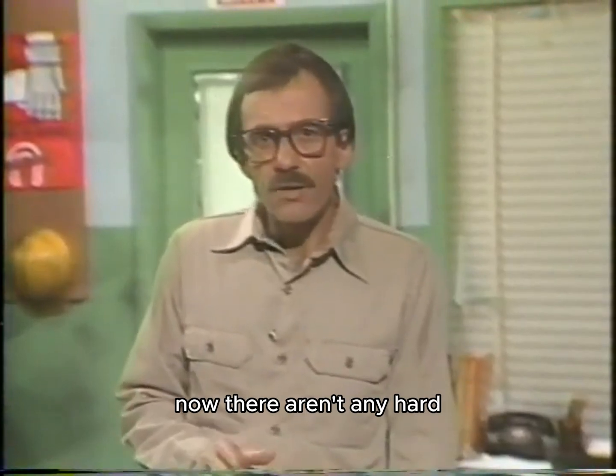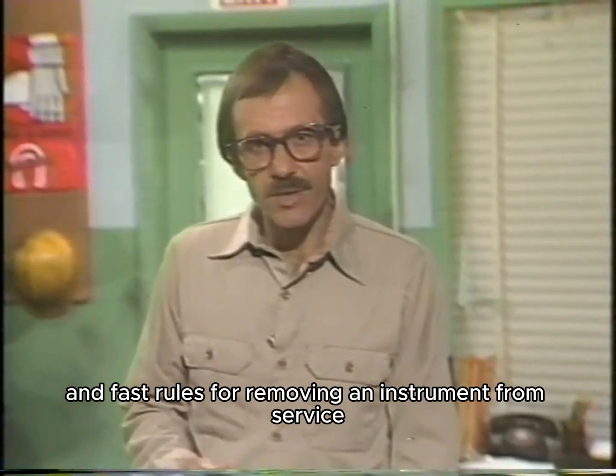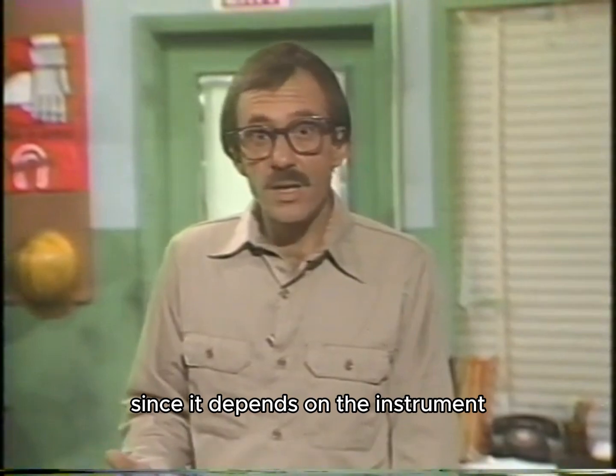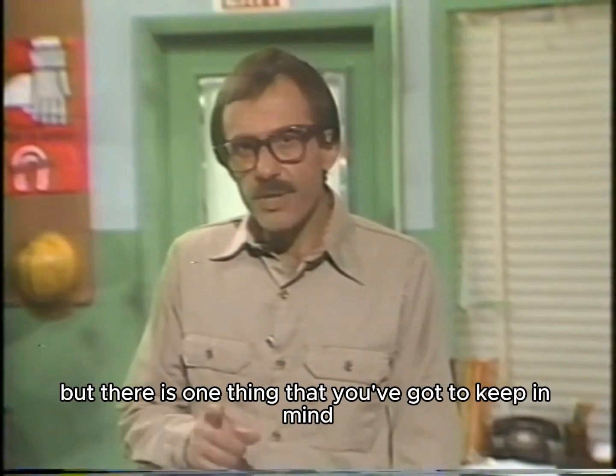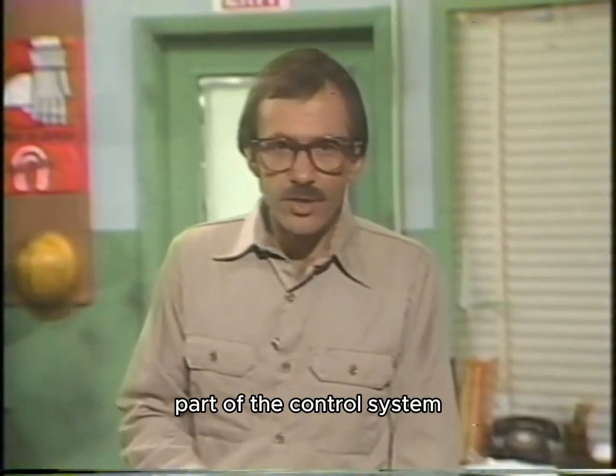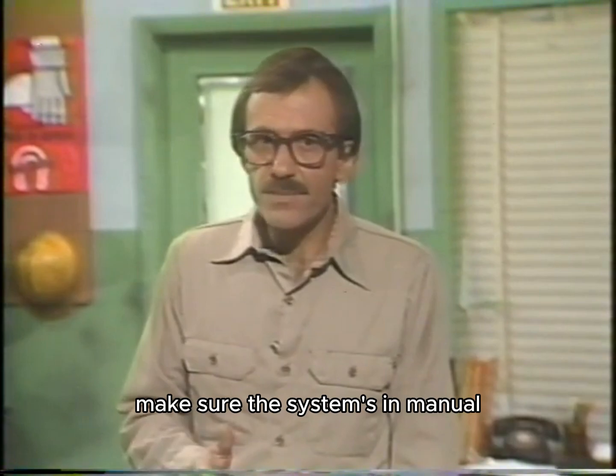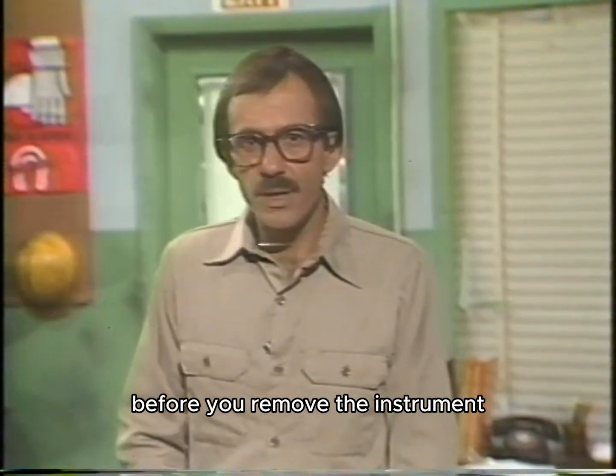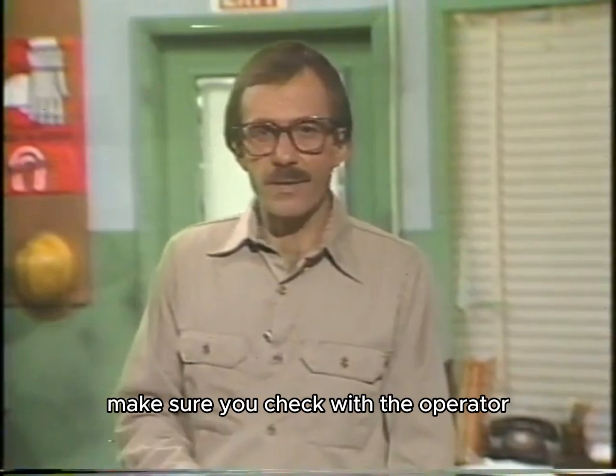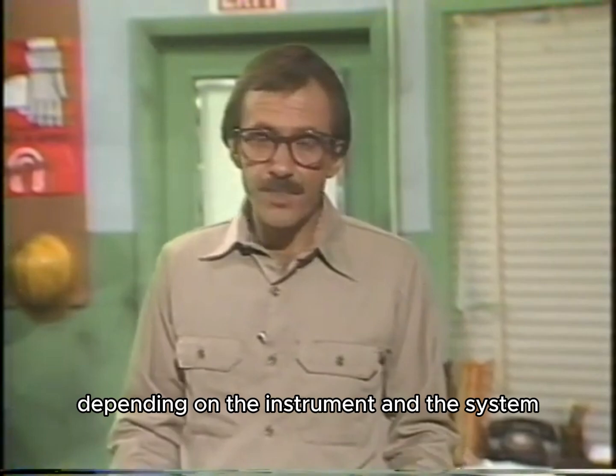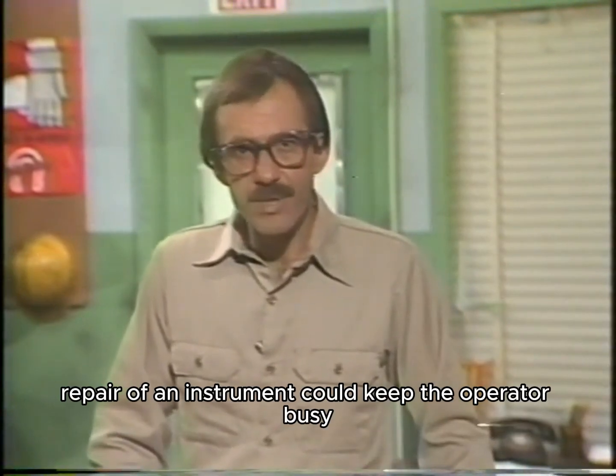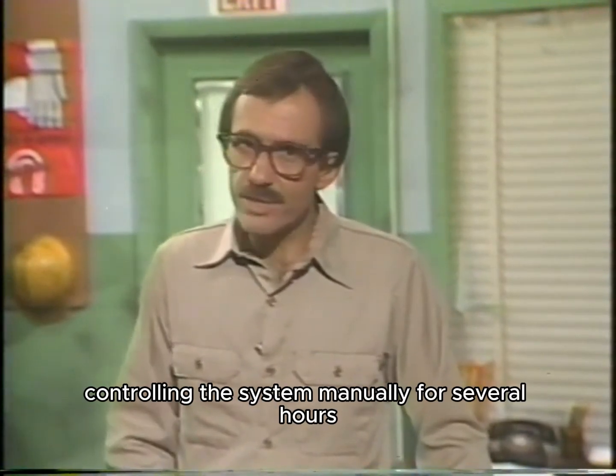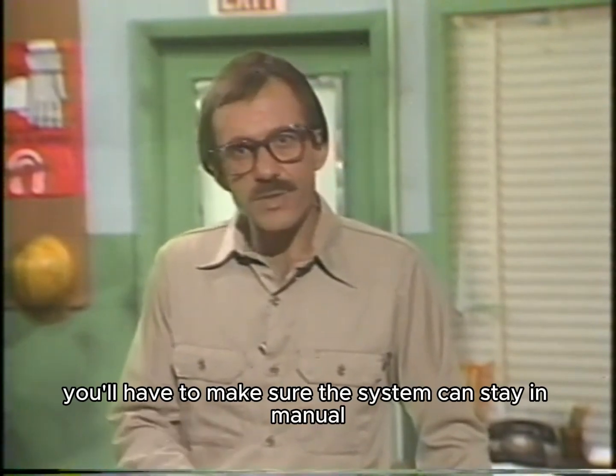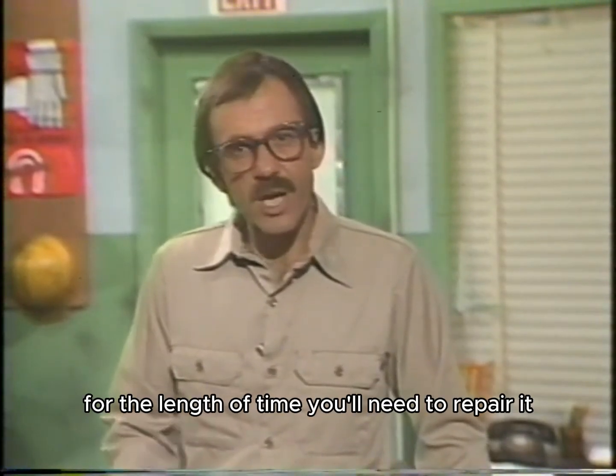Now, there aren't any hard and fast rules for removing an instrument from service, since it depends on the instrument and the type of process. But there is one thing that you've got to keep in mind. If the instrument is an integral part of the control system, make sure the system's in manual before you remove the instrument. Make sure you check with the operator to see if it's all right with him. Depending on the instrument and the system, the repair of an instrument could keep the operator busy at the panel controlling the system manually for several hours. You'll have to make sure the system can stay in manual for the length of time you'll need to repair it.